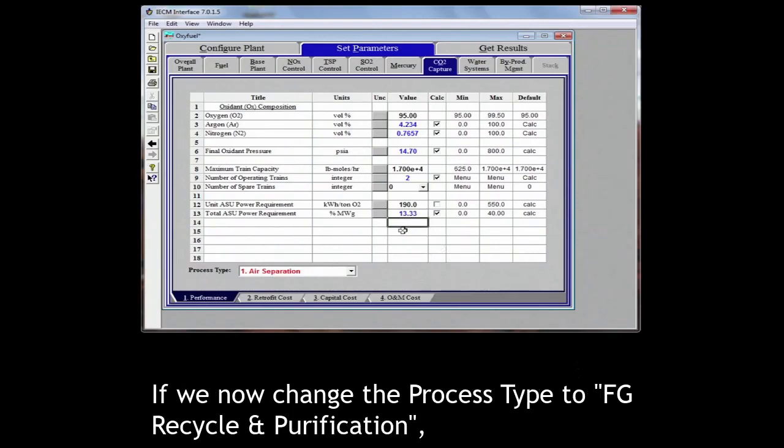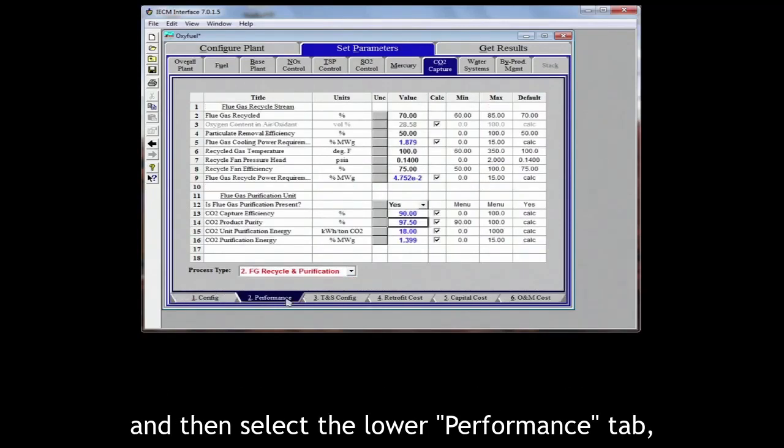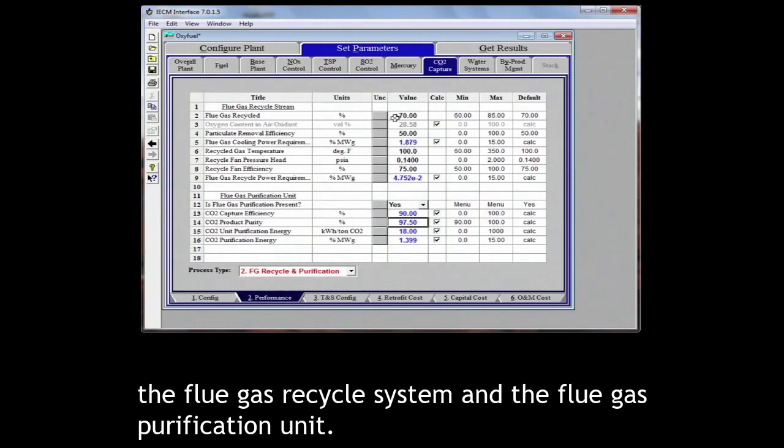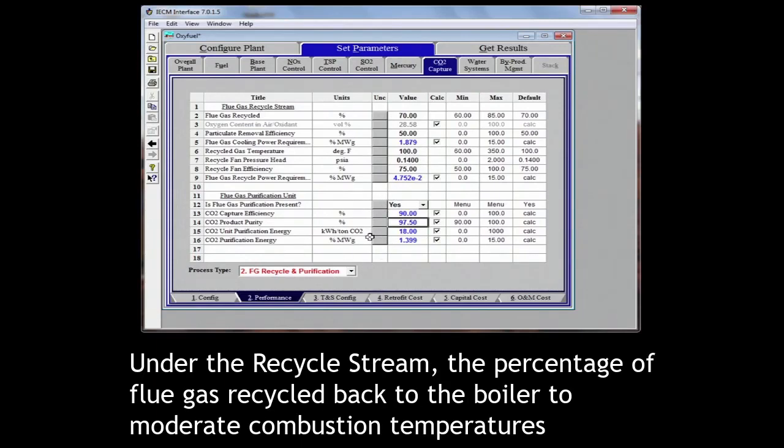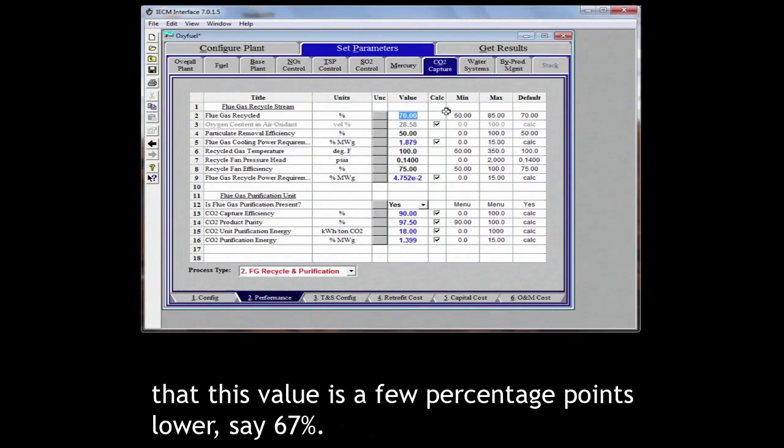If we now change the process type to FG recycle and purification and then select the lower performance tab, we can see the default performance parameters for both the flue gas recycle system and the flue gas purification unit. Under the recycle stream, the percentage of flue gas recycled back to the boiler to moderate combustion temperatures is set at a default value of 70%. For this example, we will assume that this value is a few percentage points lower, say 67%.